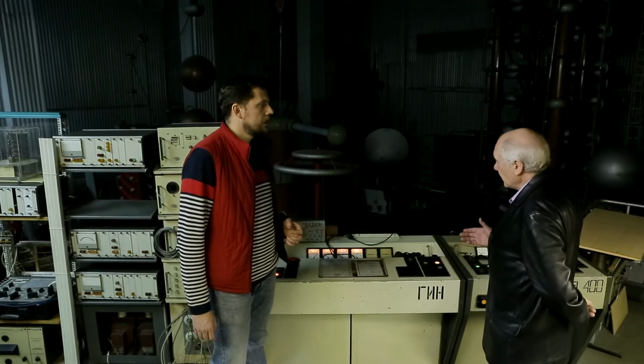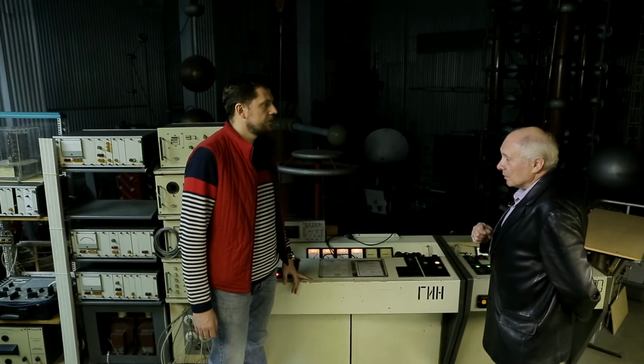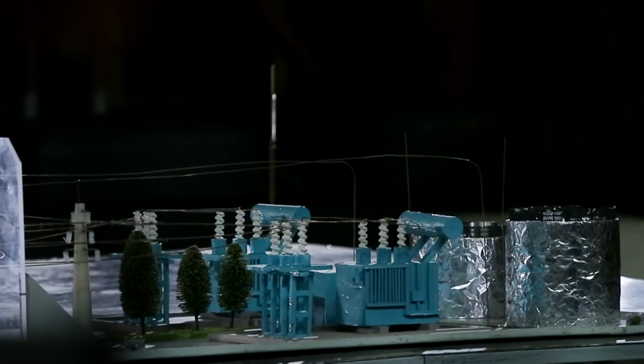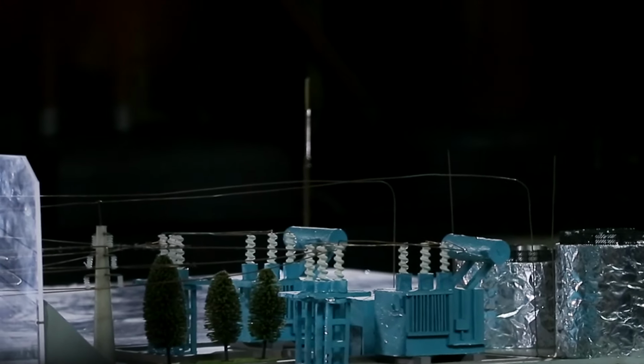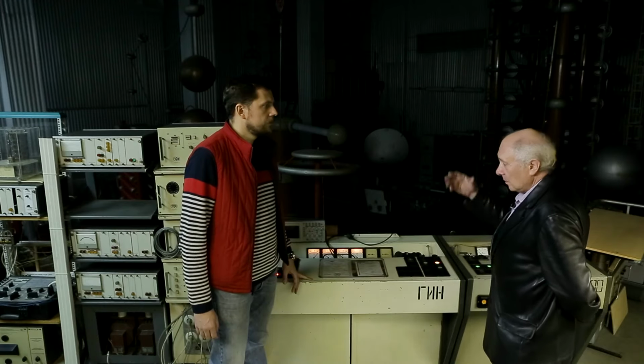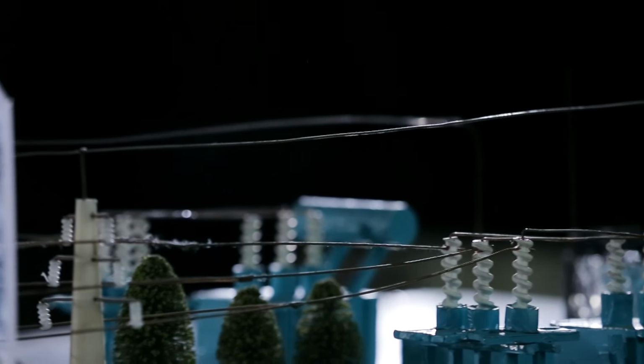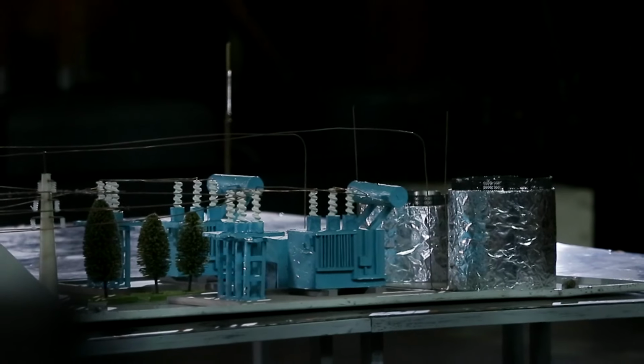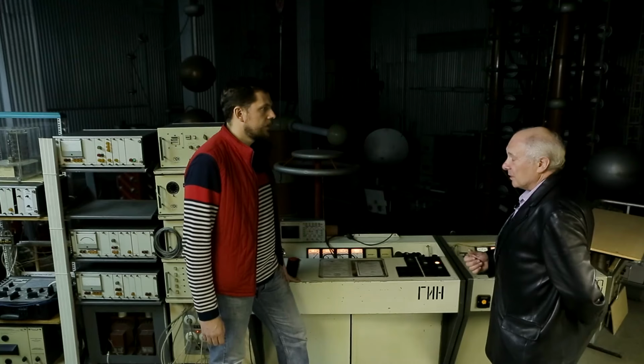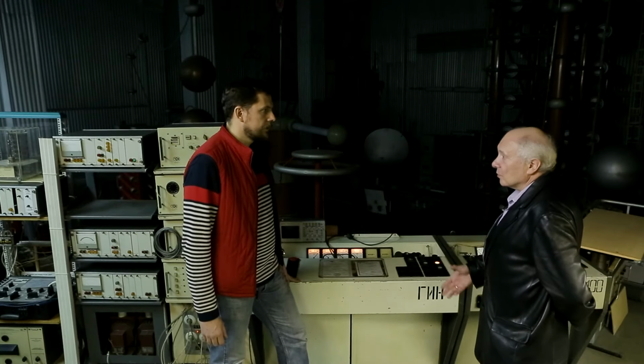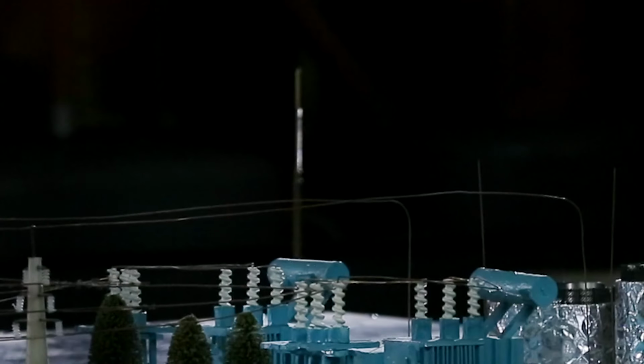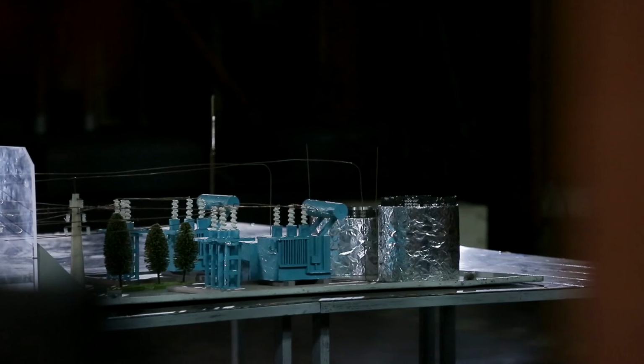For a power transmission line with a voltage class of 110 kilovolts and above, cable lightning receivers are used, which are installed above the phase wires connecting each support. And these lightning protection cables are connected to the supports. And each support is, as a rule, a reliably grounded metal structure. These constructions are tested on the same laboratory models, and the cable lightning receivers regularly take on new and new lightning. This system works practically without failures, and yet there are rare hits in the phase wires.